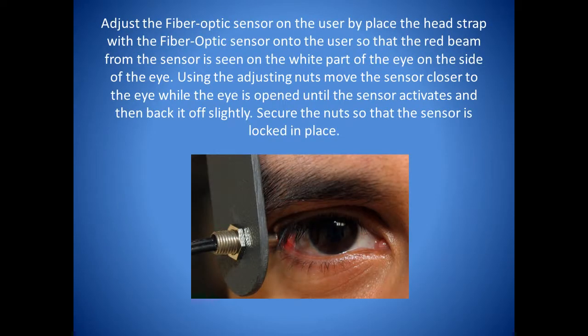Adjust the fiber optic sensor on the user by placing the head strap with the fiber optic sensor onto the user so that the red beam from the sensor is seen on the white part of the eye on the side of the eye. Using the adjusting nuts, move the sensor closer to the eye while the eye is opened until the sensor is activated, and then back it off slightly. Secure the nut so the sensor is locked in place.